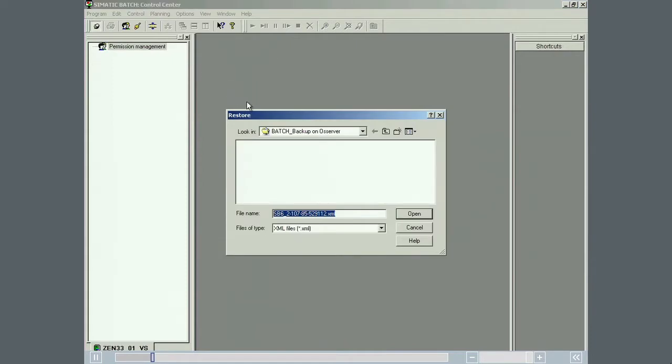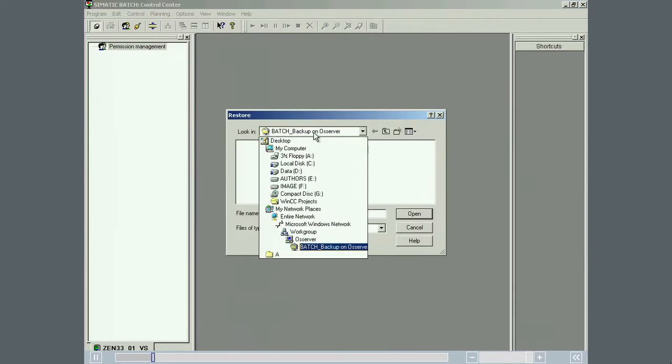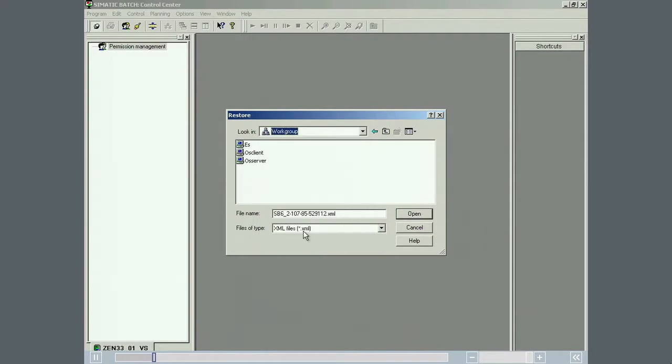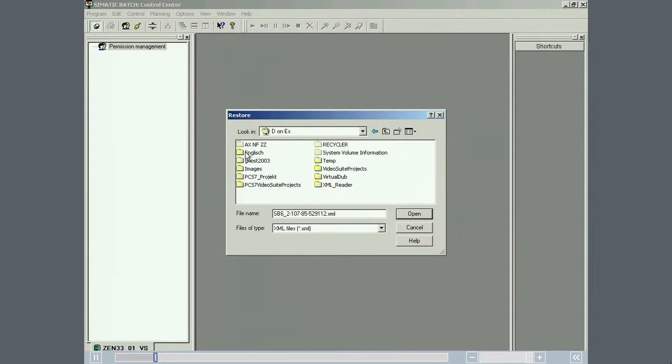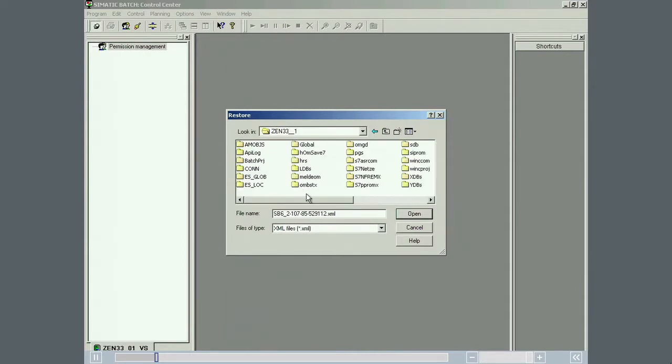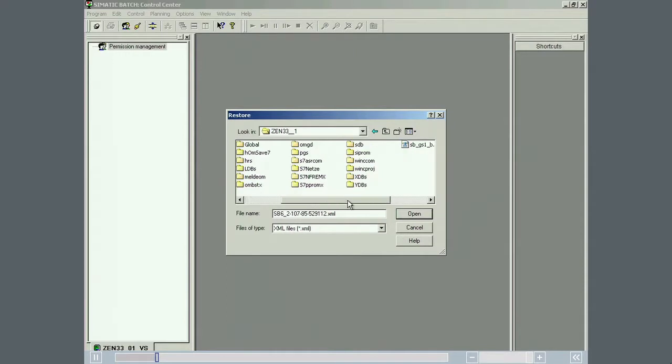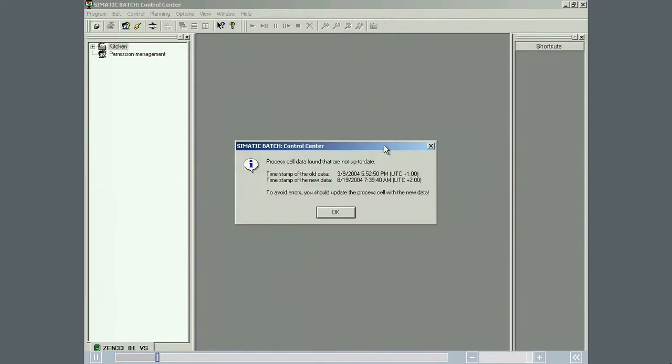The recipe database is stored in the engineering station as an XML file. The XML file format was chosen because it's a text format and will be supported in the foreseeable future. The message that the process cell data needs to be updated is acknowledged.